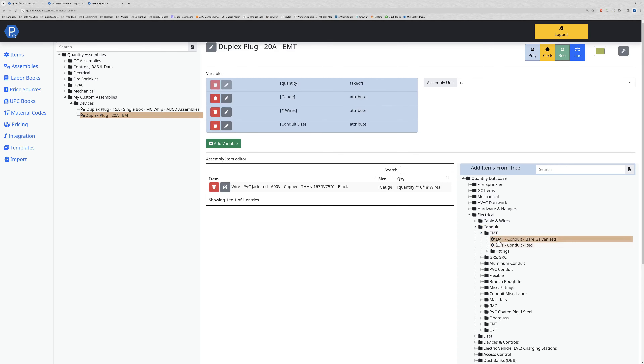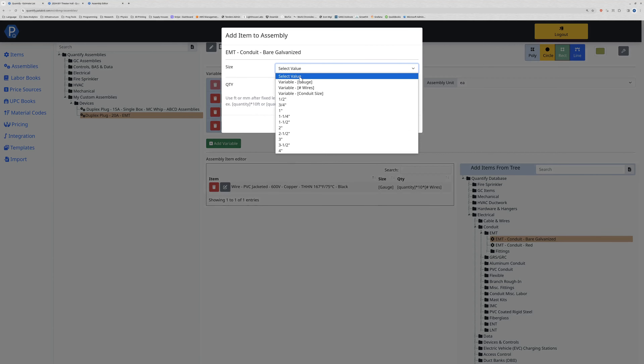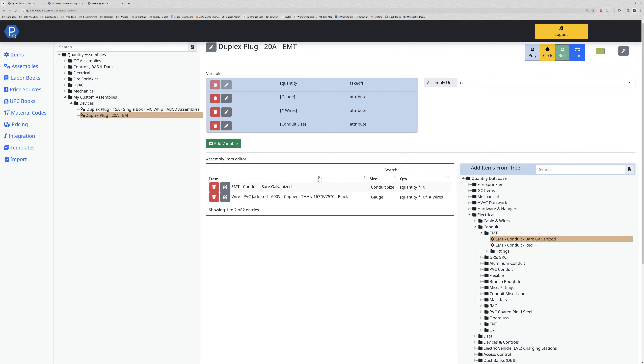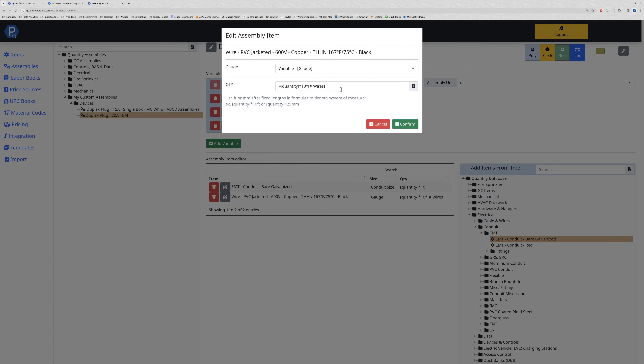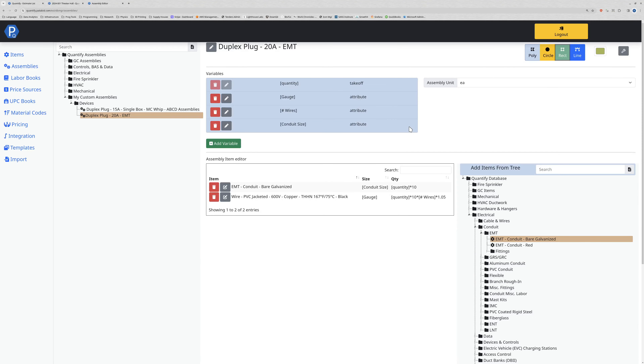I'll select conduit - I'm going to use bare galvanized EMT - attach the conduit size variable to it, and bring in quantity times 10. I notice I did not allow for any cut length on my wire, so I can go back and change that formula and put times 1.05 to add a five percent waste factor. It's entirely up to how you would do your installations.